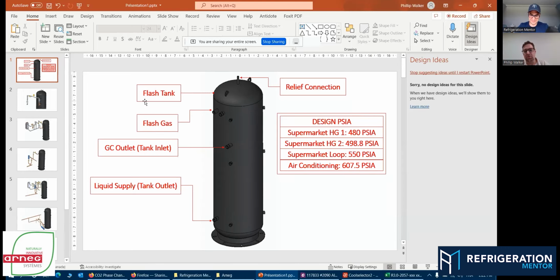When you're working on a flash tank, really think about how the manufacturer designed it. Sometimes you'll see 2 inlets, or you might just have one on the very top. If you're doing air conditioning, or maybe a CO2 system with a CO2 liquid pump, maybe a liquid pressure amplification pump like an LPA, you may have a lot less flash gas in the system. So you might just be pulling from the top of the tank, or the top of the tank might be connected directly back to the compressors, almost like an intercooler design.